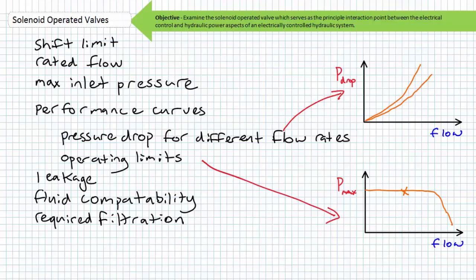Additionally, valve specifications typically describe the amount of leakage at a certain viscosity and pressure conditions, with the understanding that fluid with lower viscosity, i.e. thinner fluid, will leak more, as will higher pressure applications. Valve specifications typically state the fluid compatibility, viscosity, and level of filtration required for proper operation. The valve seals must be assessed for compatibility with the temperature and fluid being used in your application. Most manufacturers offer a choice of nitrile, fluorocarbon, or special purpose seals.